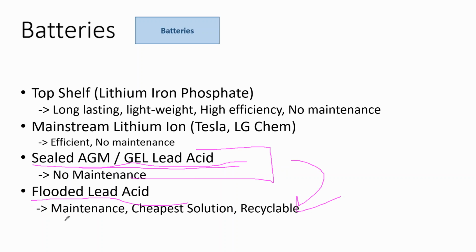That's because you get advantages within the lead acid sector if you let the gas not be captured inside the battery, but be released and vented to atmosphere. And you gain some longevity of that lead acid, which means you can cycle it more deeply if you're able to recharge the battery all the way up to the top and burst some of the plaque off of that anode to get dissolved into the electrolyte.